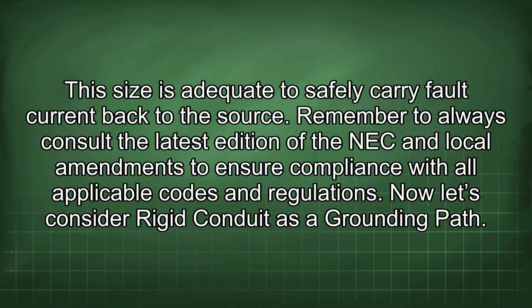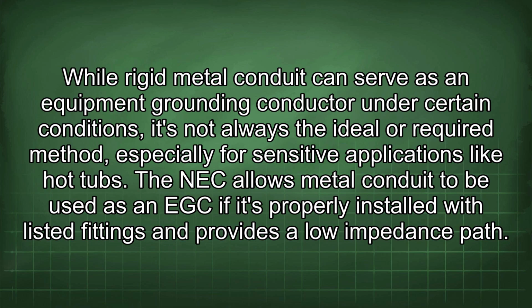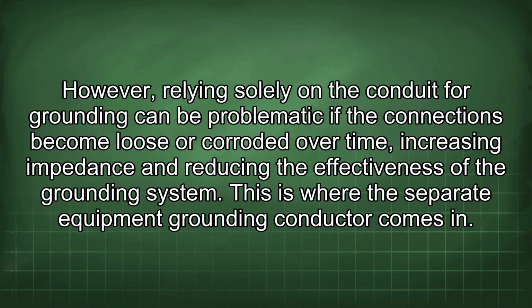Now let's consider rigid conduit as a grounding path. While rigid metal conduit can serve as an equipment grounding conductor under certain conditions, it's not always the ideal or required method, especially for sensitive applications like hot tubs. The NEC allows metal conduit to be used as an EGC if it's properly installed with listed fittings and provides a low impedance path. However, relying solely on the conduit for grounding can be problematic if the connections become loose or corroded over time, increasing impedance and reducing the effectiveness of the grounding system.